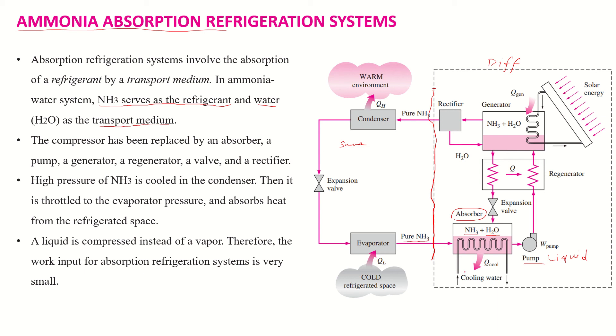We need to cool down this solution using cooling water circulation. You can see here that cooling water is circulated through these coils. This is done to reduce the temperature of the solution, because as we reduce the temperature, a greater amount of ammonia is absorbed. The function of the absorber is to absorb ammonia vapors into water.